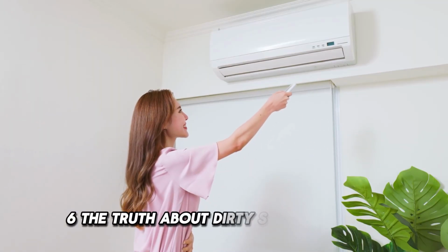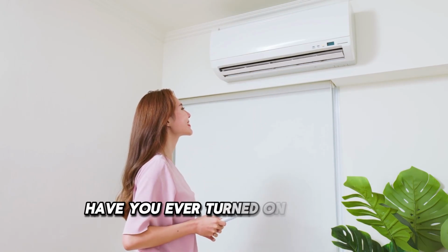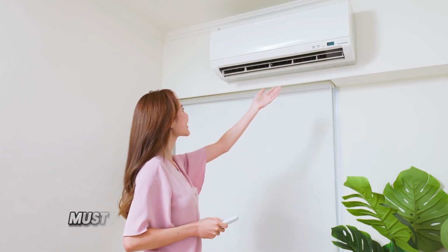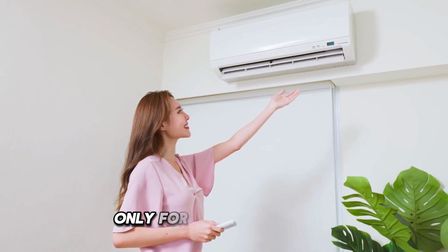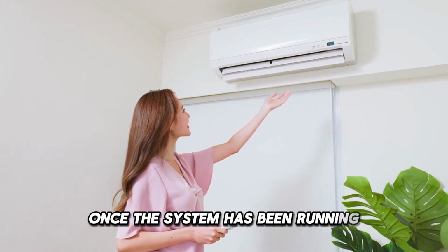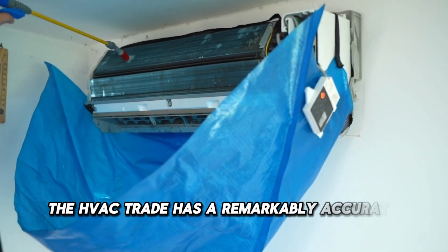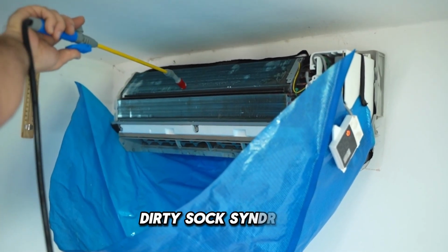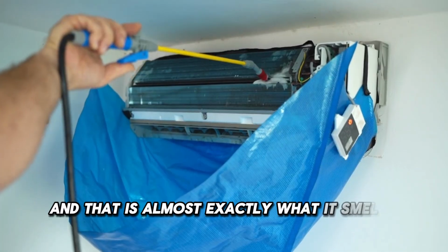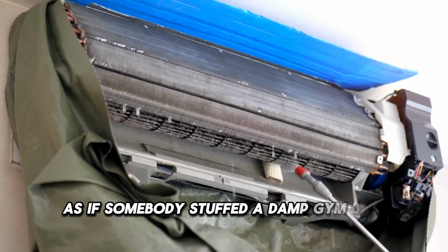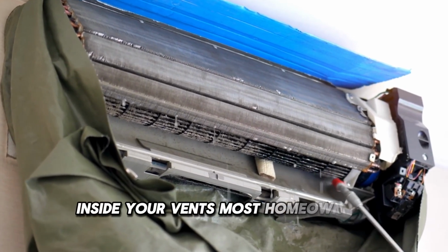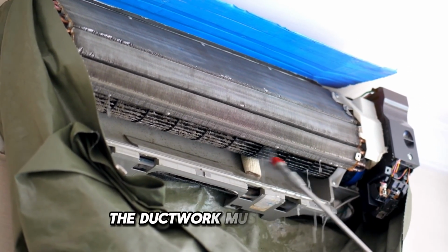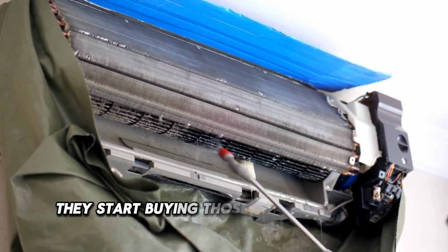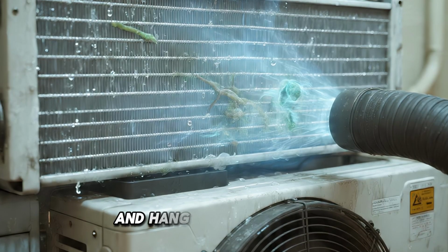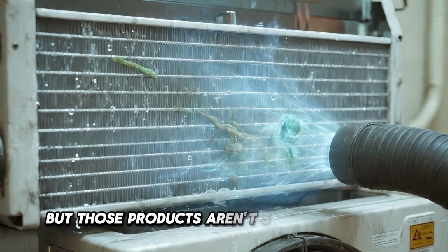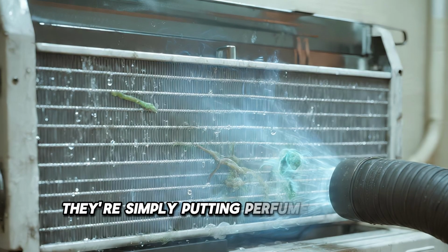6. The truth about dirty sock syndrome. Have you ever turned on your air conditioner and been hit with a strange, musty odor for the first minute or so, only for the smell to fade once the system has been running? The HVAC trade has a remarkably accurate name for this: dirty sock syndrome. And that is almost exactly what it smells like, as if somebody stuffed a damp gym bag somewhere inside your vents. Most homeowners immediately assume the ductwork must be filthy. Then they start buying those $11 a month vent deodorizers and hanging air fresheners. But those products aren't solving anything. They're simply putting perfume over the symptom.